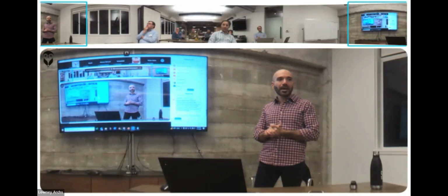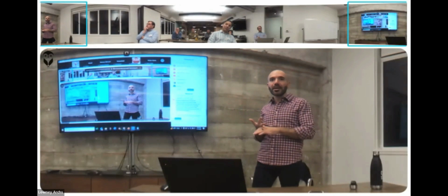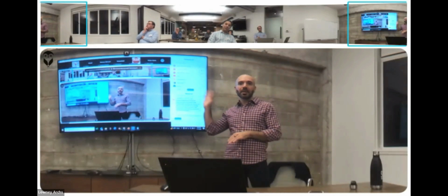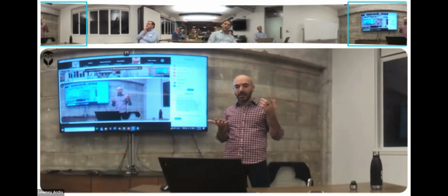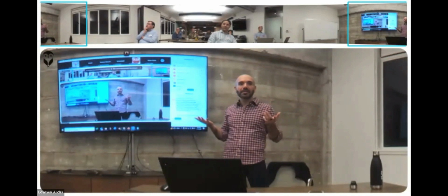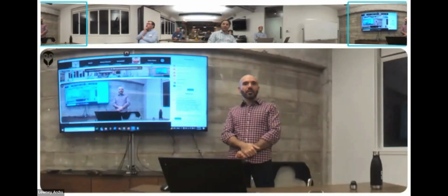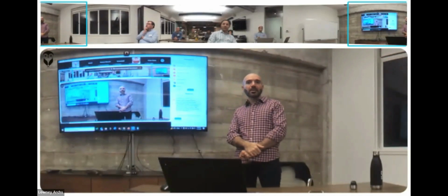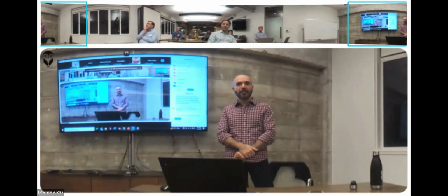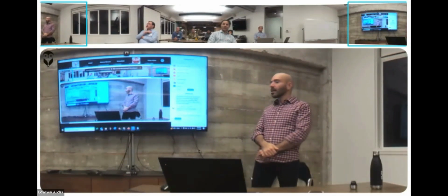If you're looking at microgrids, the code doesn't require your system to be islanded, but we're seeing most projects say, we already have a battery and the PV in the building, so I'll just spend a bit more on my controller and make it a microgrid. So when there's a fire or any disruption due to natural events, I can still have energy in my building without getting it through the grid. So there's that advantage.